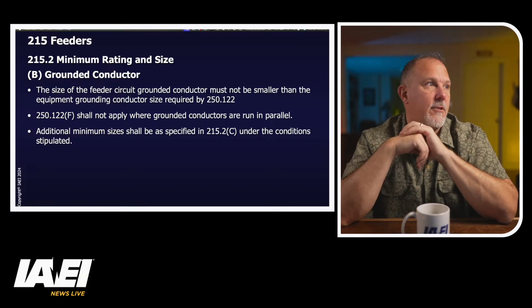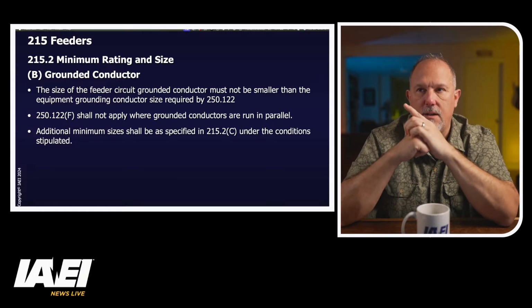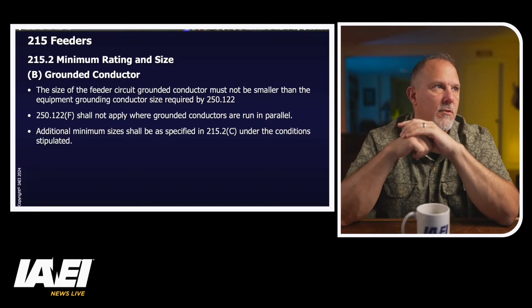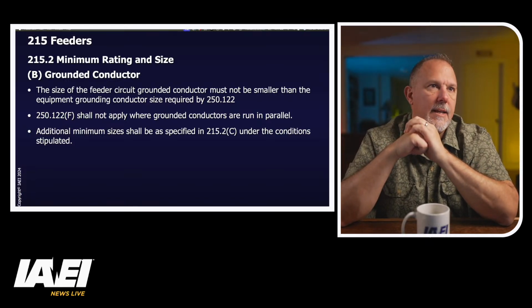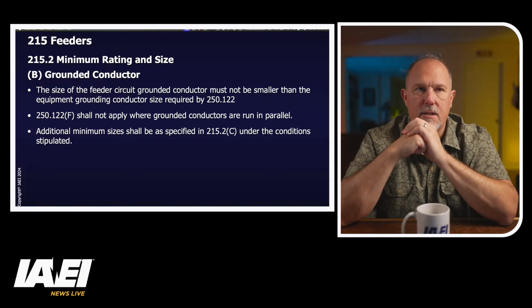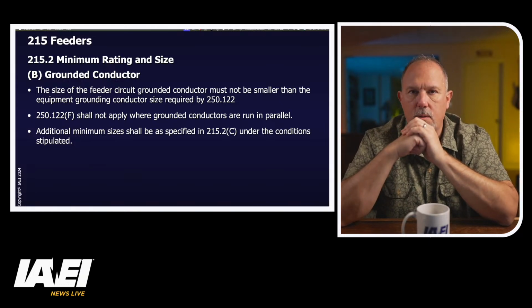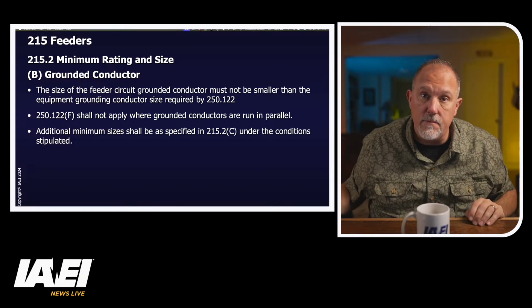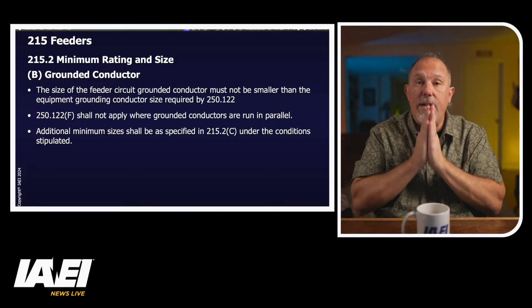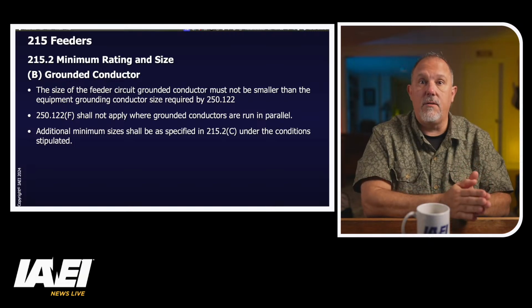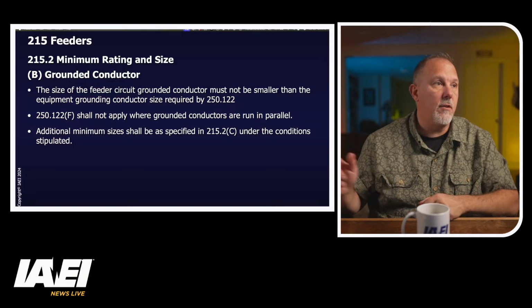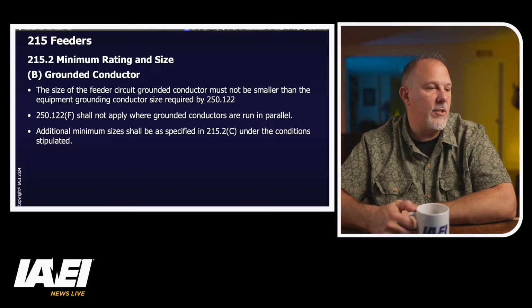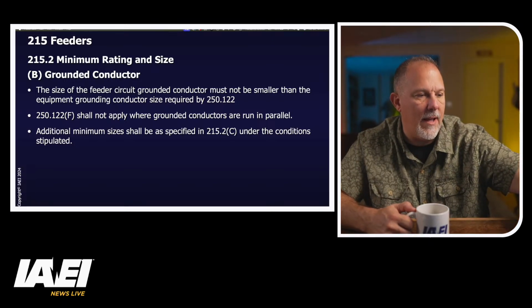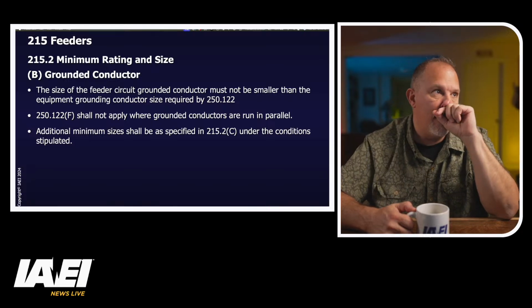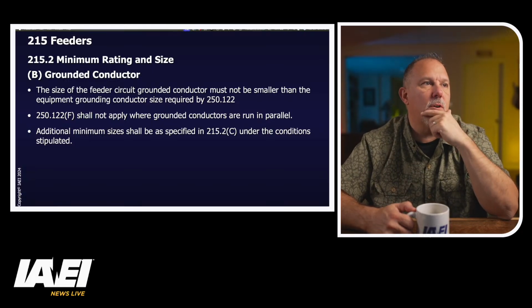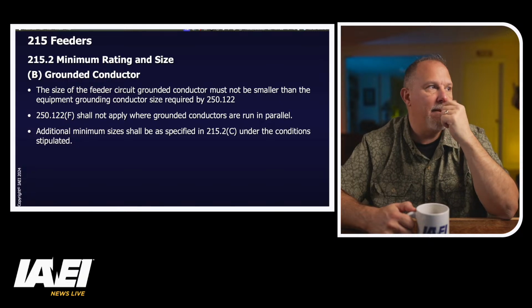250.119, 120, 122. Size of the equipment grounding conductor. Now, what 215.2 tells us is that the size of the feeder circuit grounded conductor can't be smaller than the equipment grounding conductor size required by 250.122. So that tells you just go to 250.122 and follow the rules there. We did not reinvent the wheel for 215. It points you over to 250.122. And then in 250.122(F), conductors in parallel, it says it shall not apply where grounded conductors are run in parallel.